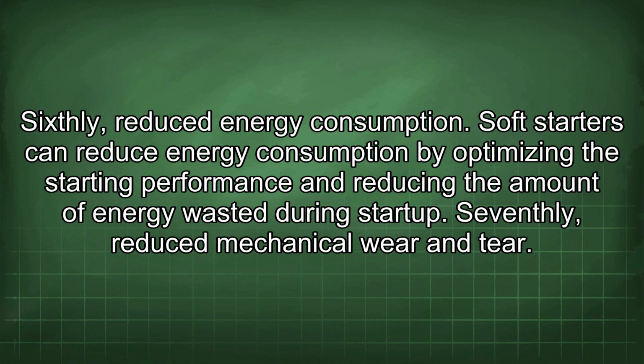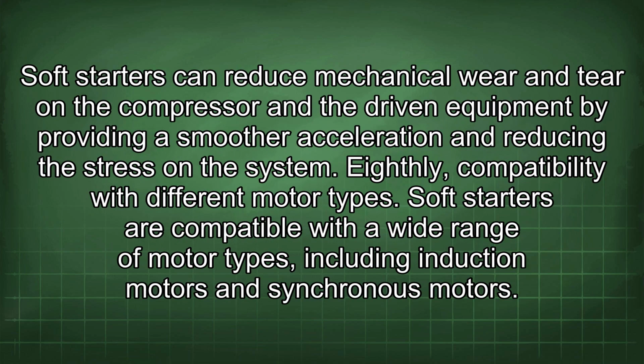Soft starters can reduce energy consumption by optimizing the starting performance and reducing the amount of energy wasted during startup. Seventhly, reduce mechanical wear and tear. Soft starters can reduce mechanical wear and tear on the compressor and the driven equipment by providing a smoother acceleration and reducing the stress on the system. Eighthly, compatibility with different motor types. Soft starters are compatible with a wide range of motor types, including induction motors and synchronous motors.